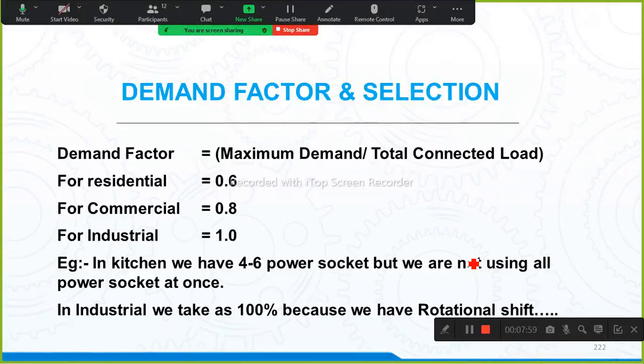In a residential building the load utilization is very low, so we take the demand factor as 60%, meaning 60% of the total load is utilized. But for a commercial building, the demand factor is given as 80%. What is this 80%? Out of your total connected building load, 80% of the load is mostly used, and 20% is not being used.